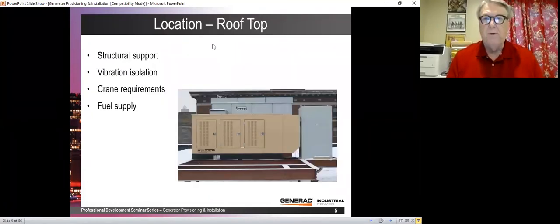Now, some people don't really have room, or they just don't want the generator to take up room and they would like to put it on a rooftop. This is not terribly common, but it's not uncommon either. I generally say anytime it's on a rooftop, you need to check with a structural engineer. Typically, if you have a generator 200 kilowatts and below, most rooftops are structurally sound enough to support that.